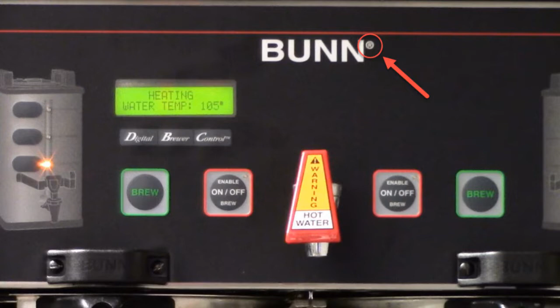our hidden button, which is located in the top right corner of the Bunn logo behind the R. This is where we access our menu settings and program our calibration. Now that we've found our hidden button, we want to carefully push in, hold for about 5 seconds to bypass brew lockout. Now that we're at units, we want to continue hitting the hidden button behind the R until we see calibration.